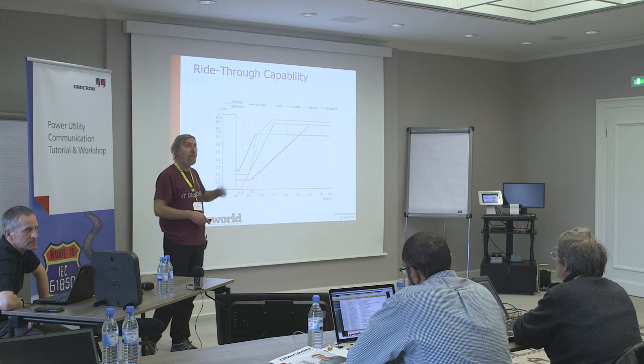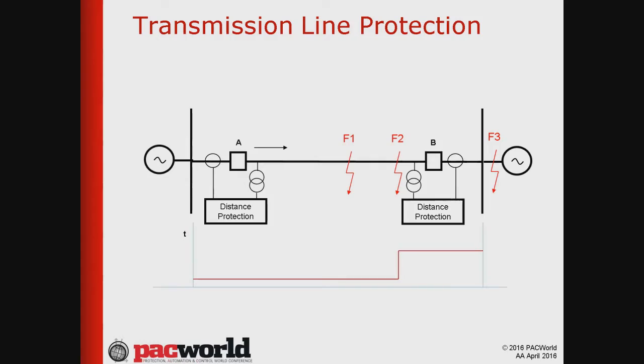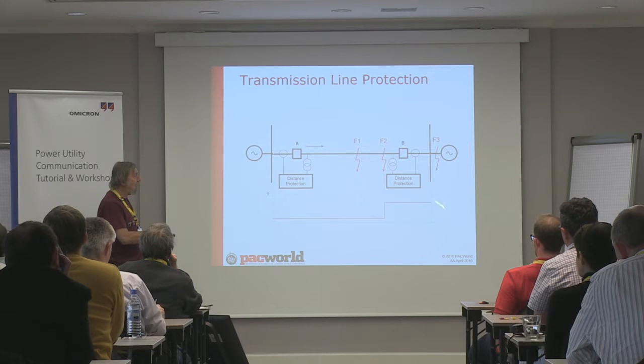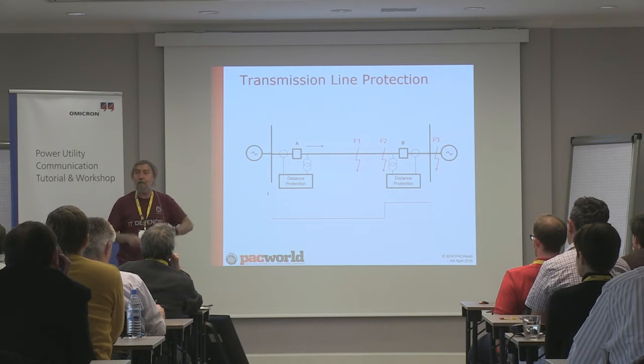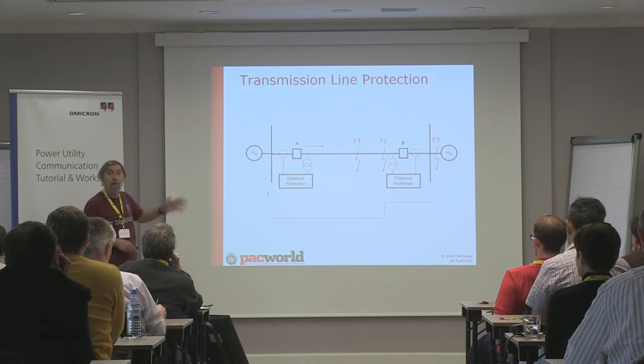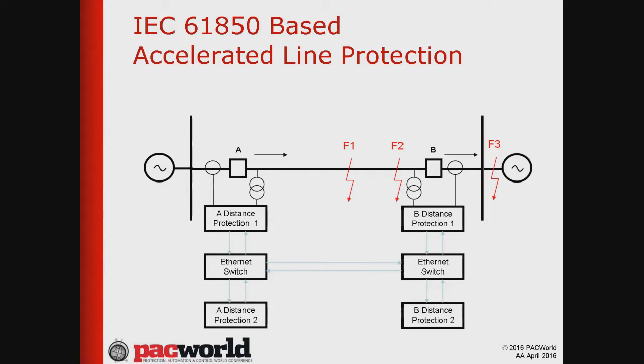And again, IEC 61850 is the solution. Why? Because if I have a fault in zone 1, it is going to be cleared without a time delay. However, if my fault is in zone 2, and depending on where in the system this is and what is the length of the line, etc., the voltage sag caused by this fault clearing, that can be several hundred milliseconds depending on the setting of the zone 2, I may lose a lot of these generators. And this is why we use what we call accelerated protection schemes.